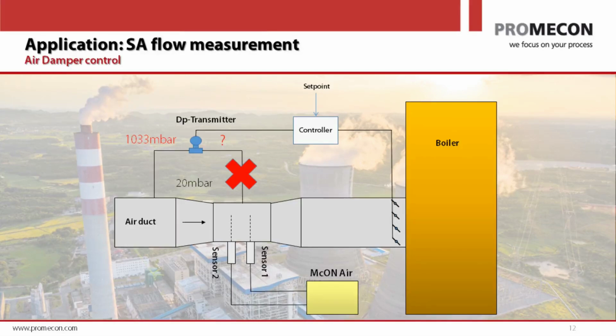So you really have a big drift in your signal. Your signal is not showing what it should show, but it's showing a deviation of 50%, 30%. You get big deviations with changes in this delta pressure by clogging or by blocked impulse lines. A very, very important thing. And the question is, what does your operator do? The question is, does your operator even see it? Does your operator even have the chance to see it? And the clear answer is no.